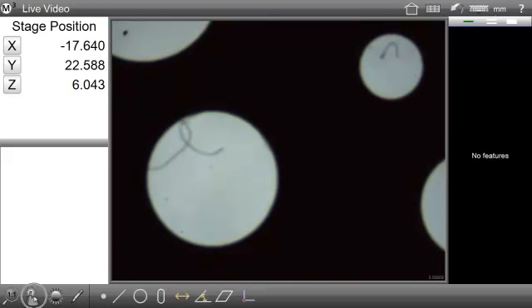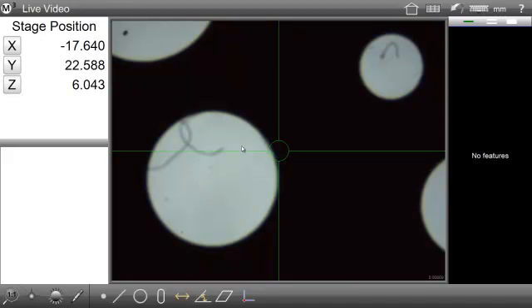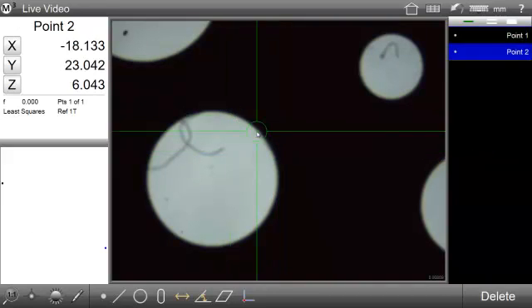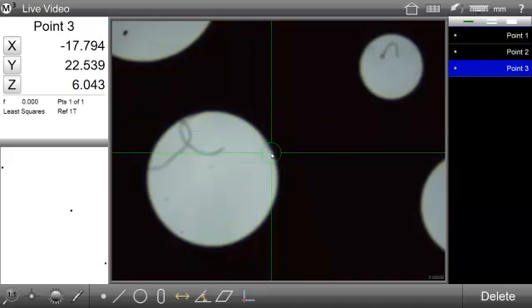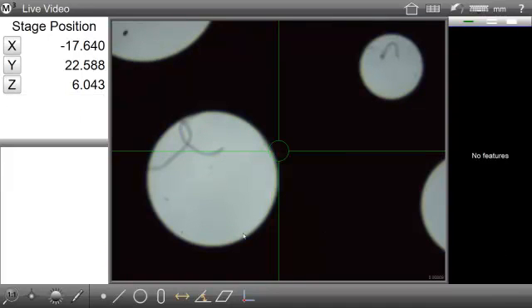The VTouch probe is simply a quicker and more efficient way of using the active crosshair probe. The ability to move the crosshair target itself instead of measuring stage makes the VTouch the optimal probe choice for the majority of measurement scenarios where the active crosshair is being used.